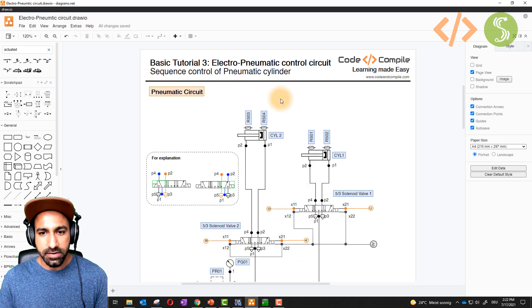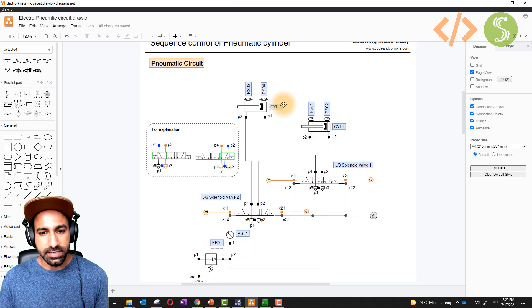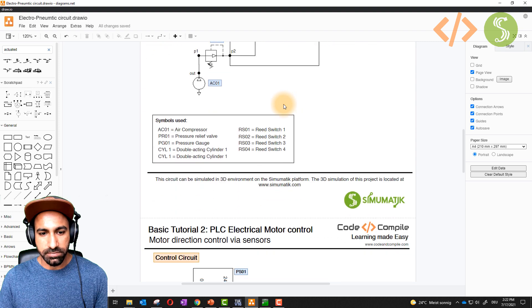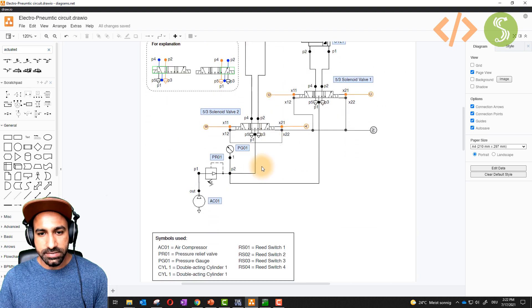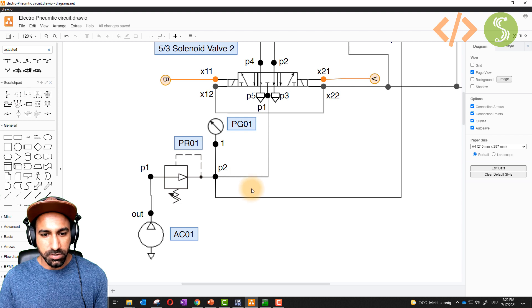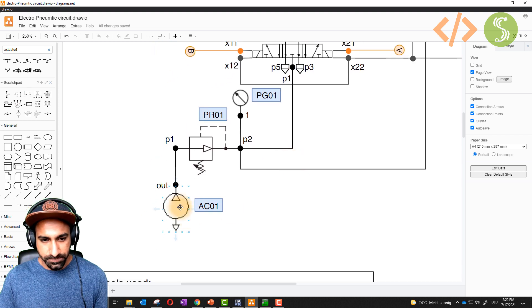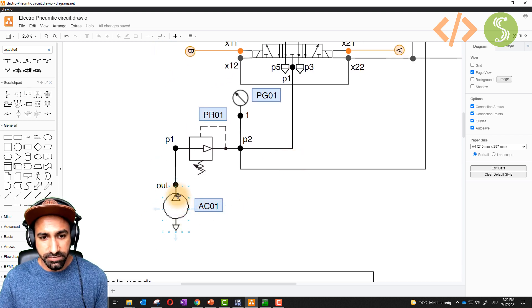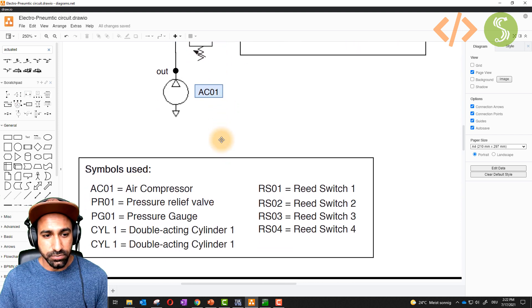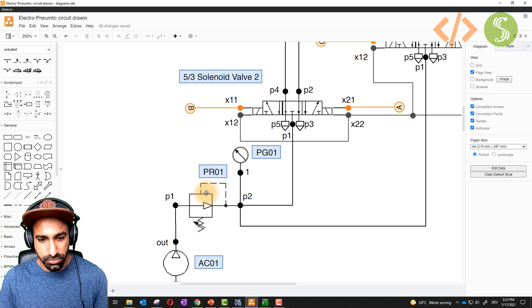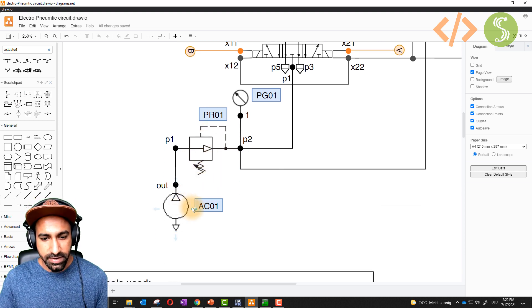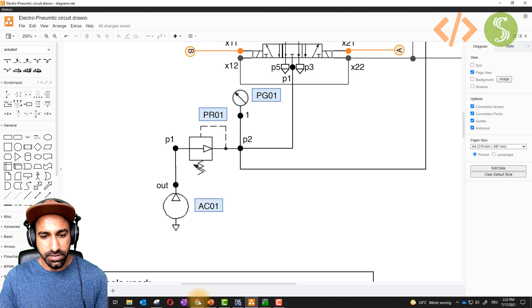In the diagram you will see the pneumatic circuit on top and a control circuit at the bottom. In the pneumatic circuit, starting from the bottom, we have an air compressor. This air compressor gives compressed air to PR01, which is a pressure relief valve used to control the pressure in the circuit. By default, this air compressor gives you six bars.